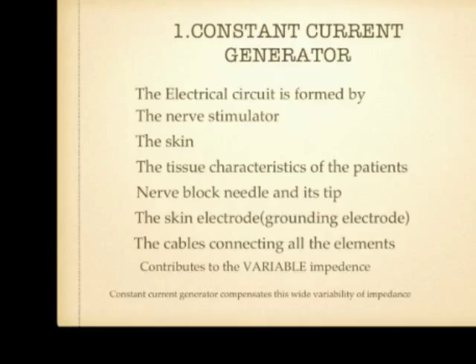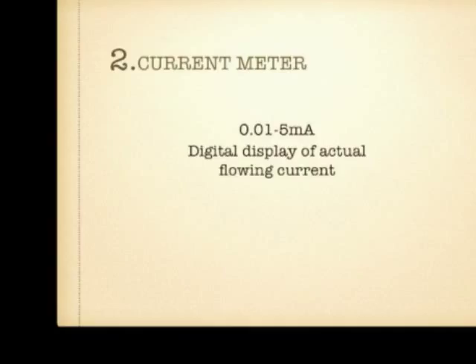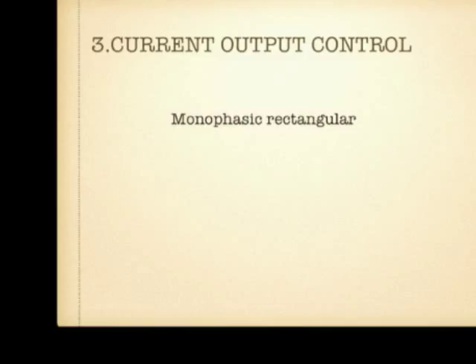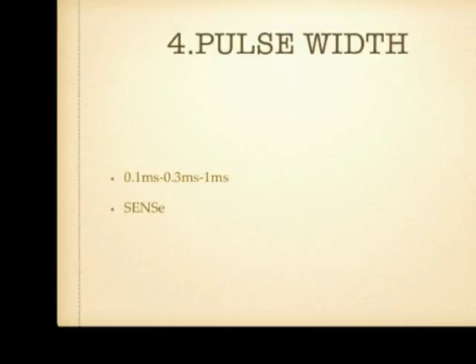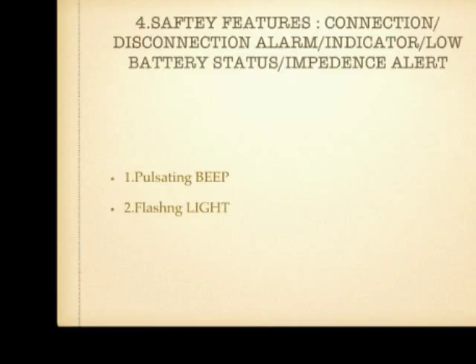The nerve stimulator should have current meters and the ability to increase or decrease current up to five milliamps, with a digital display of flowing current. You should have control of the current output. The current used should be monophasic and rectangular, meaning it goes in one direction only — from machine to patient, not back. Pulse width, or the duration of the current, should have the ability to be adjusted: 0.1 millisecond, 0.3 millisecond, or 1 millisecond duration. Newer nerve stimulators come with a SENS technique, which is sequential stimulation of nerve.